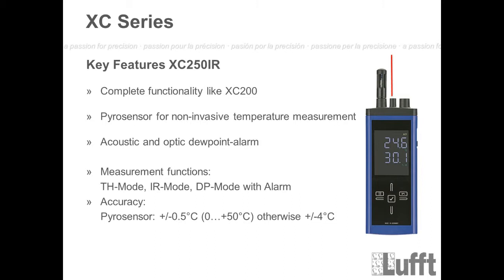That means you can enter thresholds, a low and a high threshold for the dew point, and if you will, let's say, be under this threshold, the device will start an acoustic and optic alarm. Optic means that the laser will start to blink. You will hear a beep tone with a certain frequency, and you will also see it on the display. There will be an alarm sign.